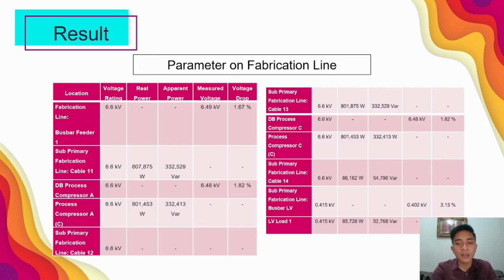In the busbar feeder 1, the line at cable 11 and 13 has the highest wattage consumed, which is 807,875 watt, then 86,162 watt at cable 14 for LV load 1. The line at cable 12 doesn't consume any power as the process compressor B was put in standby mode. The voltage at the busbar LV is rated at 0.41 kV. It is then dropped to 0.402 kV due to a few reasons such as the resistance in the cable or the type of load itself.